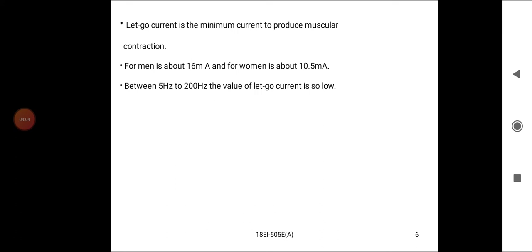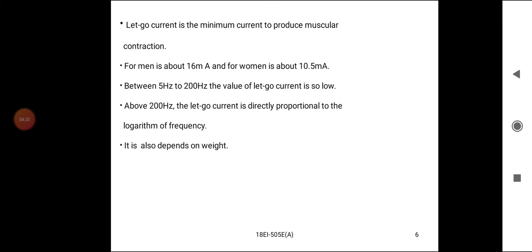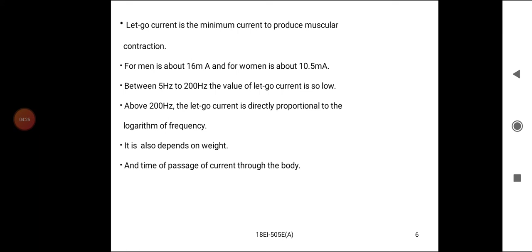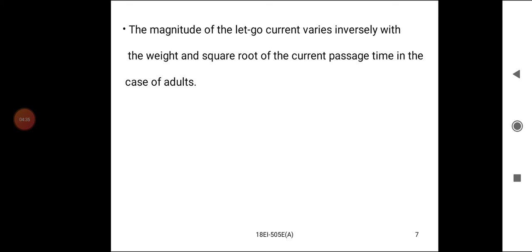Between 5 Hz and 200 Hz, the value of let go current is low. Above 200 Hz, the let go current is directly proportional to the logarithm of frequency. It also depends on weight and time of passage of current through the body. The magnitude of let go current varies inversely with the weight and the square root of the current passage time in the case of adults.